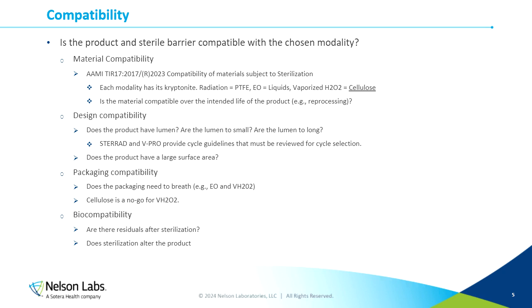For example, radiation has PTFE, Teflon. EO has limitations with liquid sterilization, and vaporized hydrogen peroxide also has its own kryptonite, and that is cellulose. So when considering your product and your packaging, that is something to be aware of, and ensure that if you're looking at that particular sterilization modality, cellulose is excluded from your product.